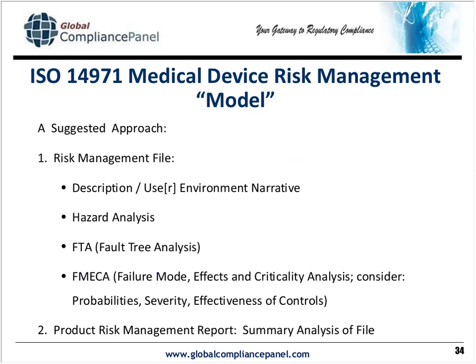And then the risk management model, again, as I mentioned earlier, I use 14971 as a model. I include a fault-tree analysis and at least 3 failure mode and effect analyses, criticality being included because I still use the risk priority numbering system. You don't have to, but I still find it usable, and I use it as a means to justify how far I drill down on validations and failure investigations, etc. Anyway, your failure mode analysis may be an FMEA or FMECA.